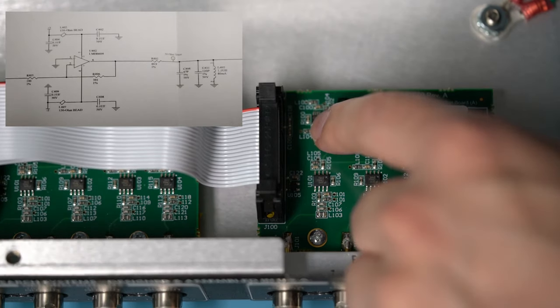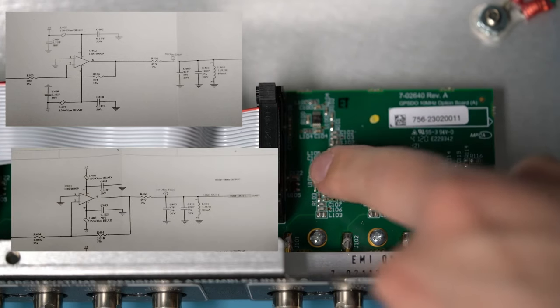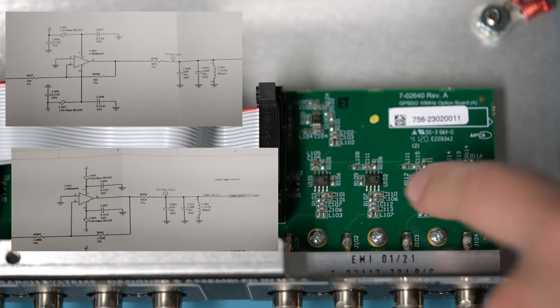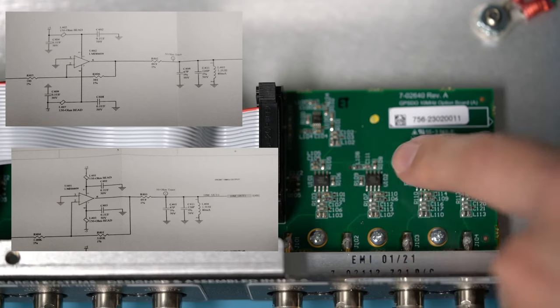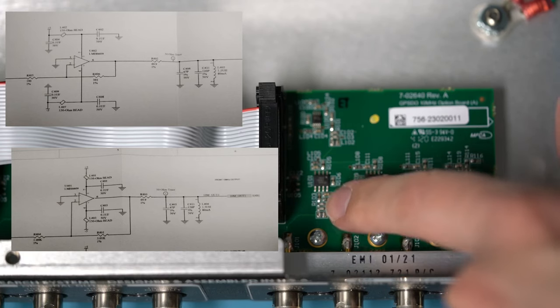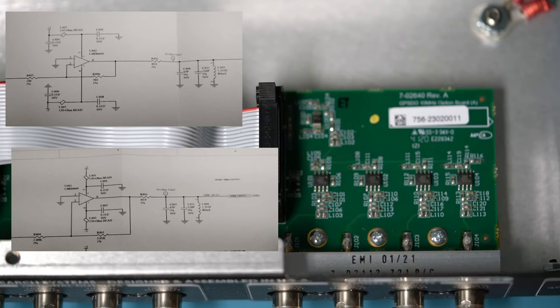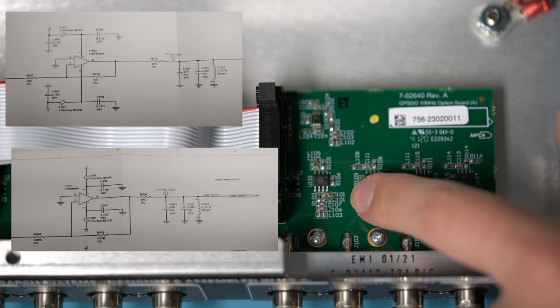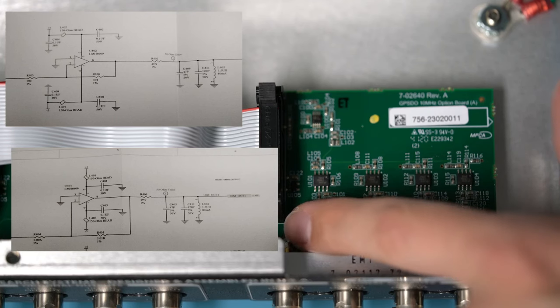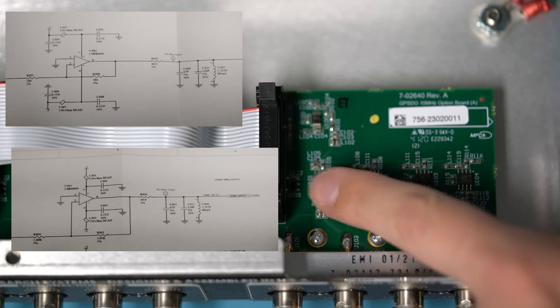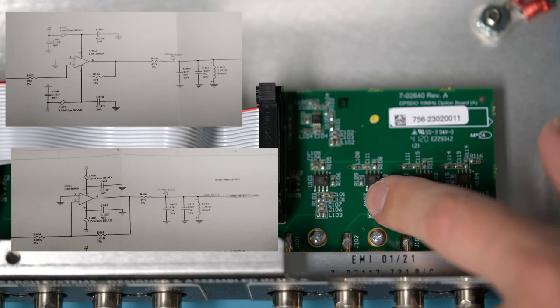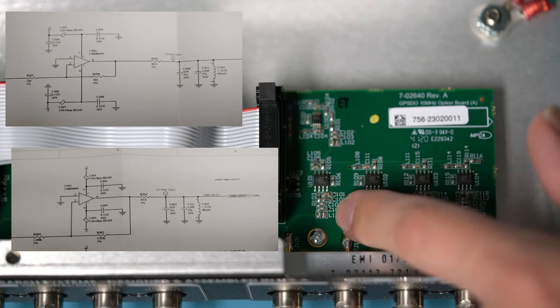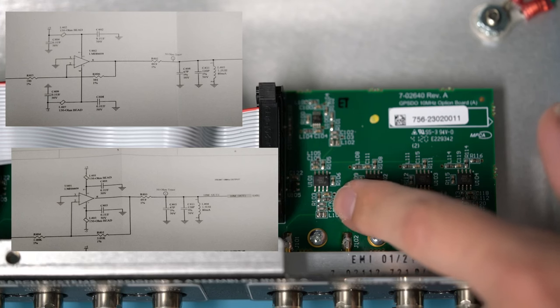We have a single amplifier at the input by the ribbon cable driving four additional amplifiers, one for each of the outputs. Each of these amplifiers has a filter network on the output to prevent any harmonics or noise from getting into the output. We want a really nice pure sine. And additionally, since all the outputs are buffered, if there's any bad terminations or noise or anything injecting undesired stuff into the clock coming out of one port, it's not going to be able to back feed into any of the other clocks and mess up another instrument.